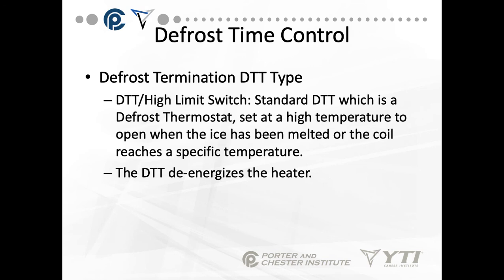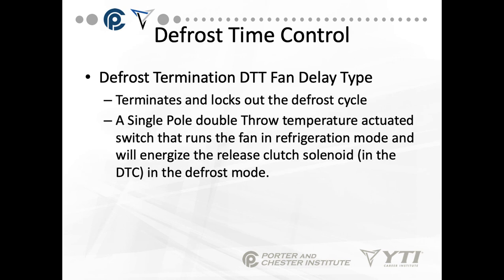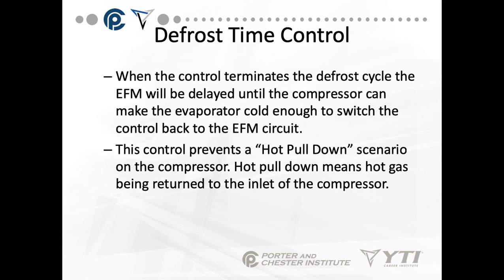The defrost termination type is basically a high limit switch — a standard DTT, or defrost thermostat. It's set to a high temperature to open when the ice has been melted or the coil reaches a specific temperature. The DTT also de-energizes a heater; if there's electric heat, the DTT will act as a high limit and de-energize the heater as well. If it's a fan delay type, it terminates and locks out the defrost cycle. Then the single-pole double-throw temperature-actuated switch that runs the fan in refrigeration mode will keep the fan off until the coil has reached a cooler temperature. When the control terminates the defrost cycle, the evaporator fan is delayed until the compressor can make the evaporator cold enough to switch the control back to the evaporator fan motor circuit.